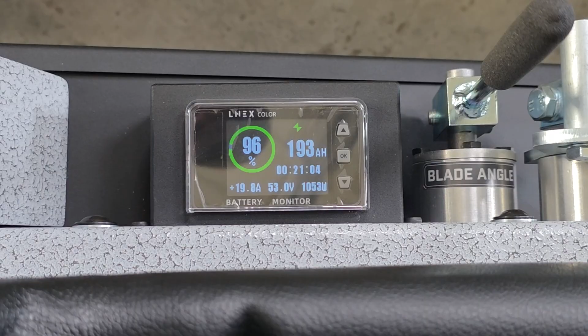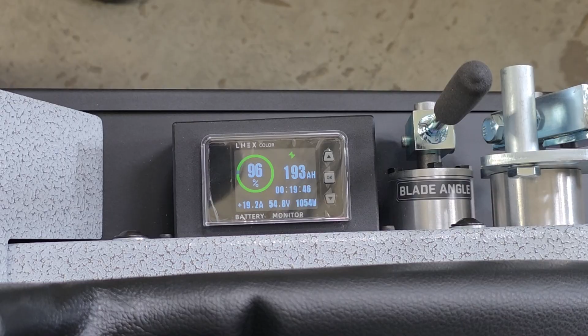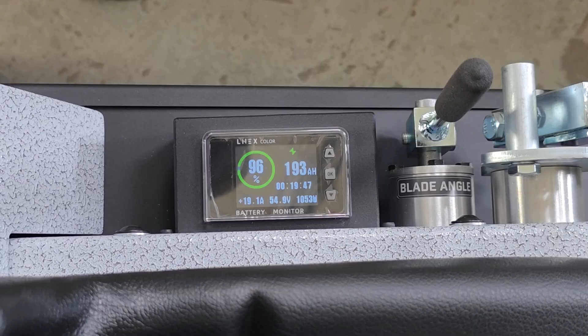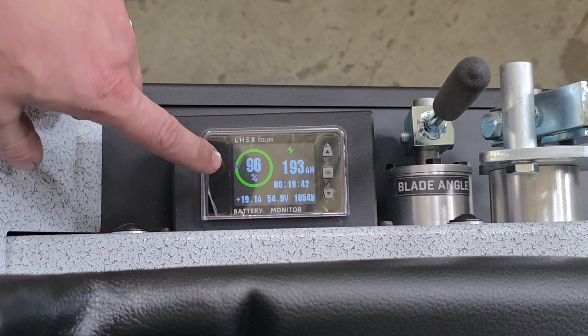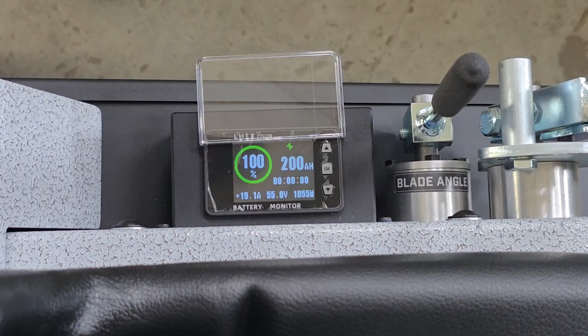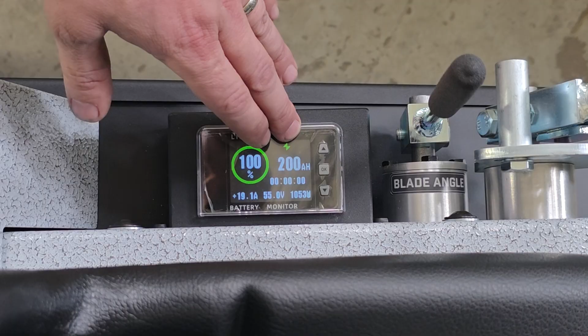After your machine has been used over a number of cycles, it may be necessary to reset the battery monitor to show 100% when the battery's at a full charge. You'll know that it's time to do this reset if the charger has run its full cycle, as indicated by a green LED on the charger, but the battery monitor is not showing 100%. If that situation exists, open the cover and press and hold the up arrow for just a few seconds. This will reset the battery monitor to 100% and make sure that the battery monitor is in sync with the actual state of your batteries.